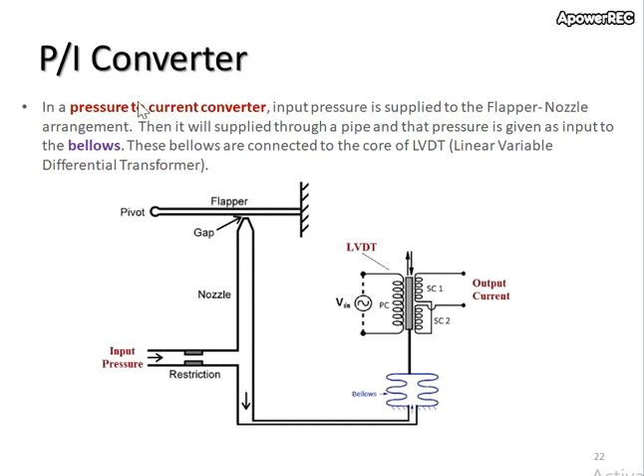This slide demonstrates the pressure-to-current converter mechanism. It is almost similar to a current-to-pressure converter, but this time the input pressure will be injected through this restriction and will flow to the bellows. The bellows will expand further if the input pressure is increased. If the input pressure is minimum, then the bellows will retract.